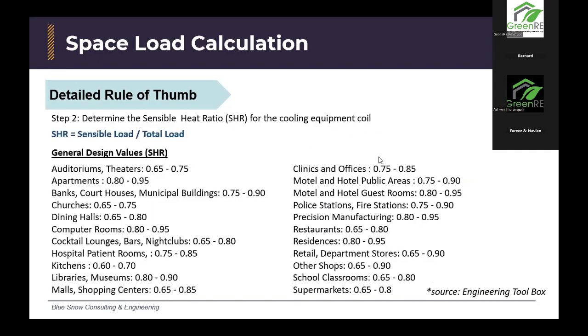So that's why it takes us to the next slide. This is what is known as SHR, which is the sensible heat ratio. It is the ratio of the sensible load over the total load. This SHR ratio is often used inside the cooling coil that is going to cool your space. The manufacturer will need to size the cooling coil to know how much sensible load I want to remove and how much latent load I want to remove, because both are getting removed in that same coil. So how you want to size that coil is also kind of a rule of thumb, but not necessarily correct. SHR ratio is based on type of space and use.